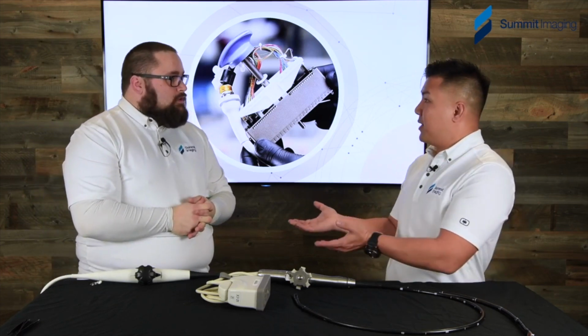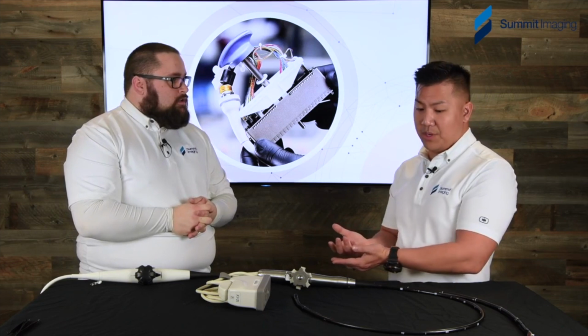Yep. But we've actually found some, you were at a site where they were using a bite guard, and we discovered why the faces of all the probes started to get nicked constantly, to the point where it would compromise the leakage test results, because it would eventually end in a crack or a puncture. Yeah. Could you tell us about what you found during that study? Well, I did find some situations where before and after the study, the transducer was just being stored with all the other surgical equipment.